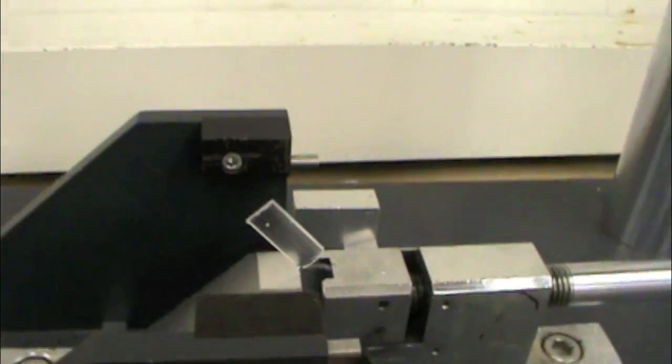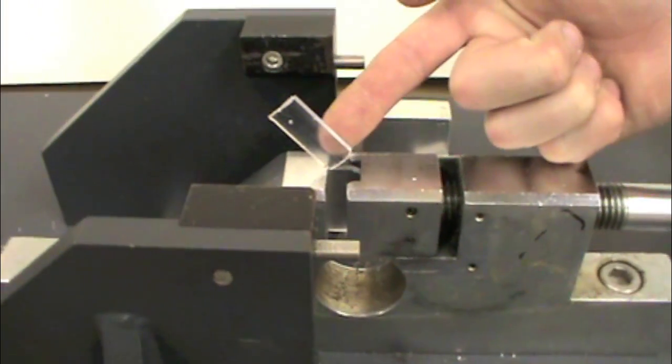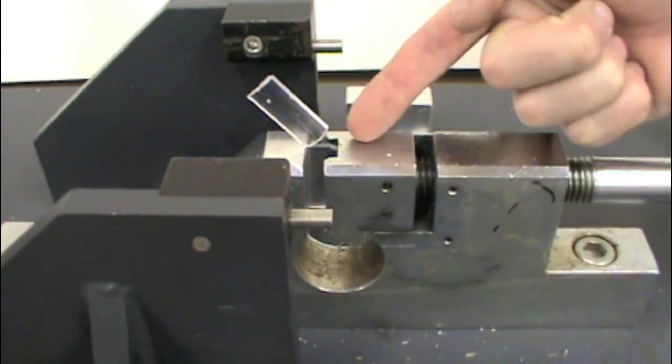Another problem that you may run into is what's called a hinge break. A hinge break looks like this. If this occurs, record the reading from the indicator needle, but note that it was a hinge break. You may want to use a heavier pendulum arm if this becomes a recurring issue.